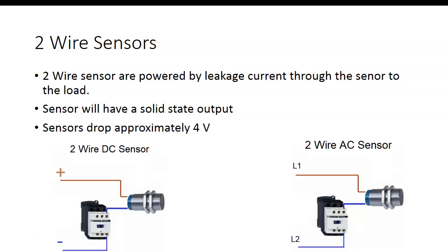So we got to be real careful hooking these contacts in series, because the contacts aren't real, they're simulated. If I put 2 of these sensors in series and each one drops 6 volts, then both together will drop 12 volts. We might get to where we don't have enough to operate our load. Okay, got it there?